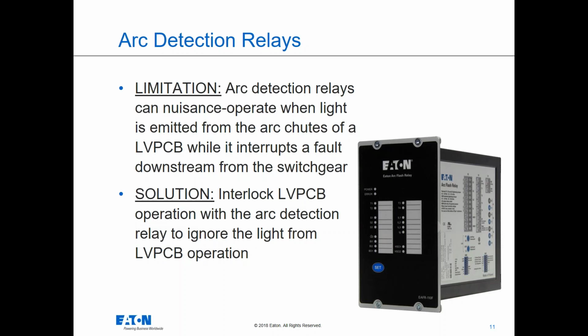The other thing that's kind of unsaid is that when you're using a light detection system, because it can't be empirically linked to the actual reduction in time by most accounts, none of the manufacturers, by applying these types of systems, can give you a direct number by which to change your model.